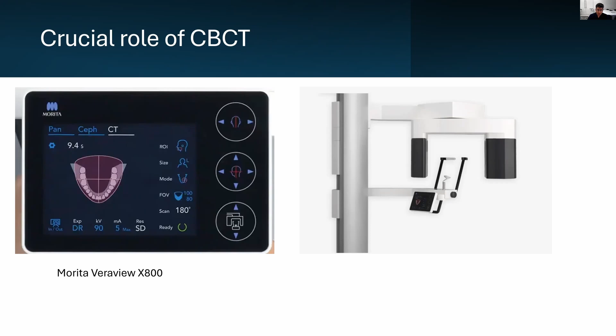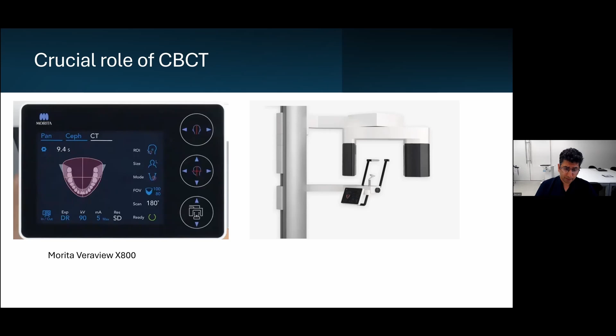And of course, I want to have a machine, and I explained this thoroughly in part 1 of the webinar, which had many settings. I wanted to have large field of view, small field of view. I wanted to be able to use half rotation scan, with 180 degrees. I wanted to have a lot of control over my scan because I want to reduce not only dose, but also scatter, and reduce motion artifact by reducing the possibility for the patient to move. And that's why having shorter scan times.